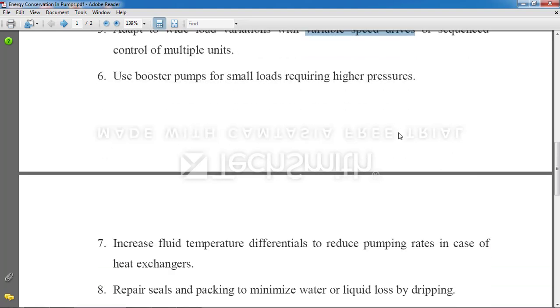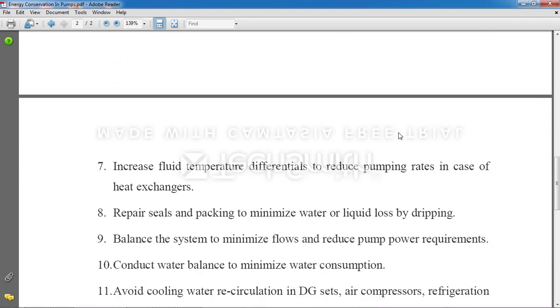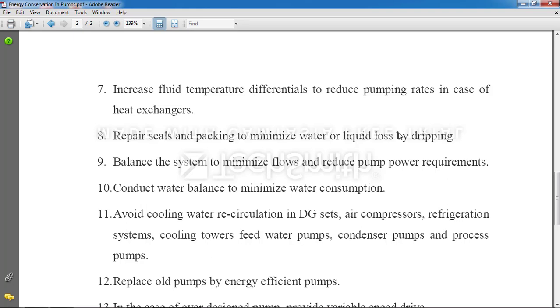Next point, use a booster pump for small loads requiring higher pressure. Now you know what a booster is, right? There are booster pumps whose flow rate is quite high for small heights, not for big heads. They are always used for small heads. Next point, increase fluid temperature differentials to reduce pumping rates in the case of a heat exchanger, right?